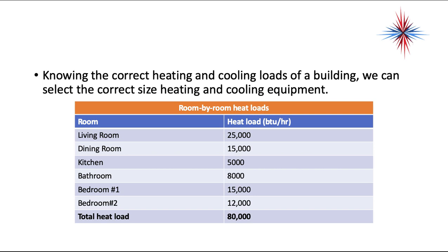What you do is perform a room-by-room heat load calculation. Once you have that laid out, you can determine your total heat load — for example, 80,000 BTUs of heating per hour. You're going to have two columns: a heat load column and a cooling load column. Knowing the correct heating and cooling load of a building allows you to select the correct size heating and cooling equipment.